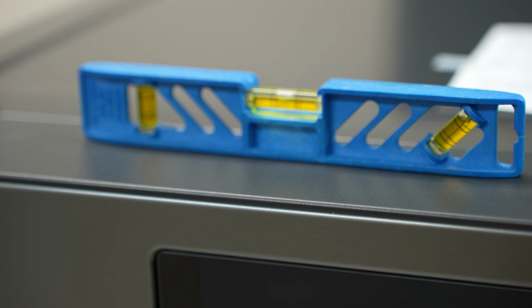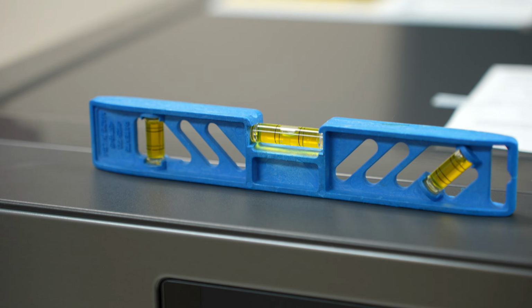So now we can run it through its initial load. Now on the machine itself, it does have an initial load thing where you have to run the initial load program that measures the weight of the product and does a calibration of it. If you don't run this calibration according to their use and care manual, you will have issues with the machine. Definitely make sure you run that calibration first and foremost before you try to run a load on this, to make sure the machine is calibrated and ready to work properly.